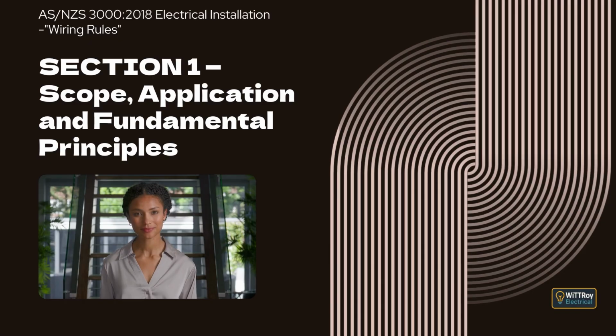Clause 1.9.2 Compliance with other standards. Some installations need to follow extra standards that apply to their specific type of equipment or environment. This clause simply reminds the designer to check which additional documents are required. Clause 1.9.3 Alterations and repairs. When you change or fix an installation, the new work must not make anything less safe. You cannot leave any part carrying more current or voltage than the standard allows, and you cannot create conditions that break the rules. Repairs should use materials and methods that were acceptable for the original installation, but they must still meet today's safety expectations.